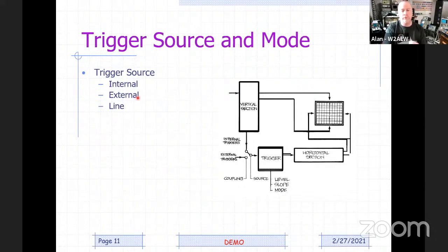So you want to look at waveforms with respect to some other signal, and that could be an external trigger source. In some cases, if you're looking at things related to the line frequency or power supply, AC line frequency, like you're looking for ripple that's synchronous to the AC line, you can simply do a line trigger. It's also a way of just getting a nice, consistent trigger. If you just want a nice waveform that's updating all the time, but you don't want to mess around trying to trigger on the signal itself, a line trigger is a nice, handy way to do that. Okay, so that's our source selections.